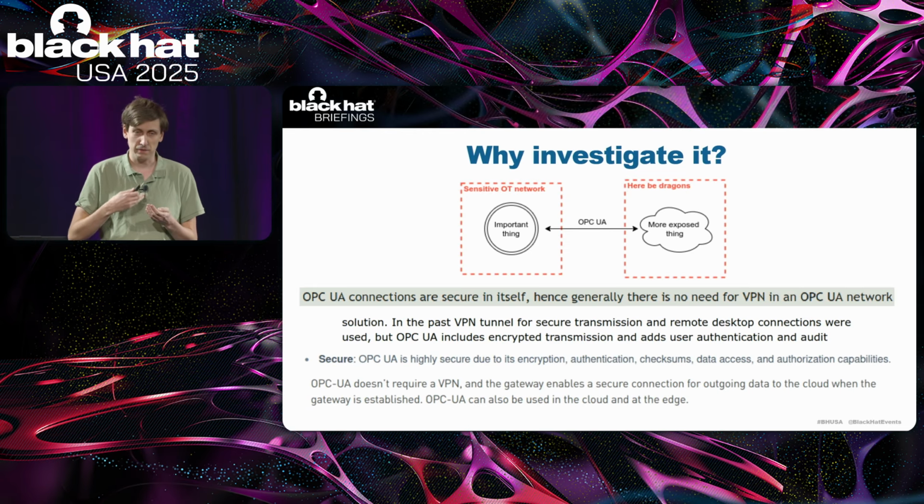And in general, it's based on two different layers: the communication layer, or the secure channel layer, that's responsible for setting up transport encryption, and for client and server authentication, which is basically the device authentication, which is what you would typically use when you have an automated system connecting. Then there's the session layer, or the application layer, which takes care of user authentication and authorization, which is generally used when you have somebody, for example, using an HMI, directly interacting with the system, entering a password somewhere. And you can use both authentication methods, or neither.